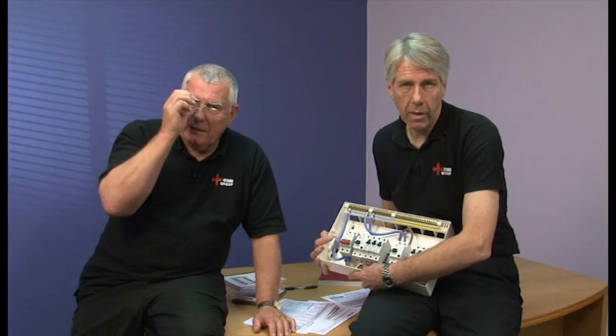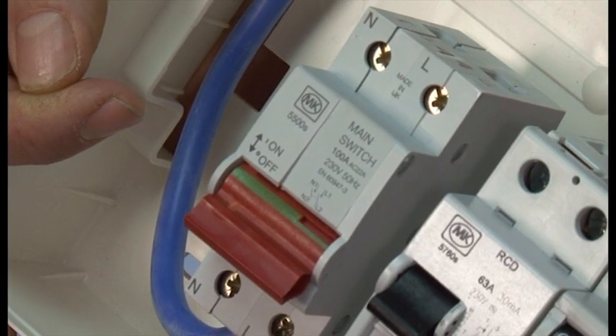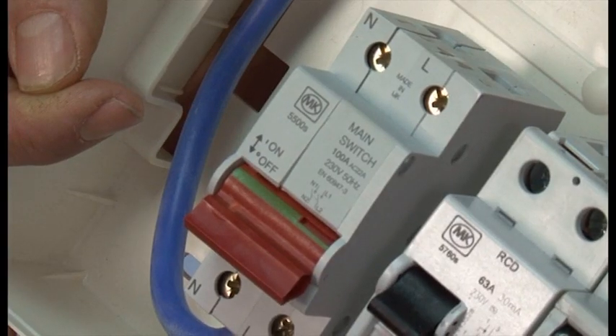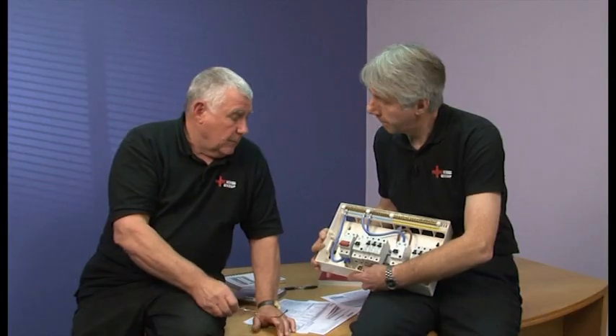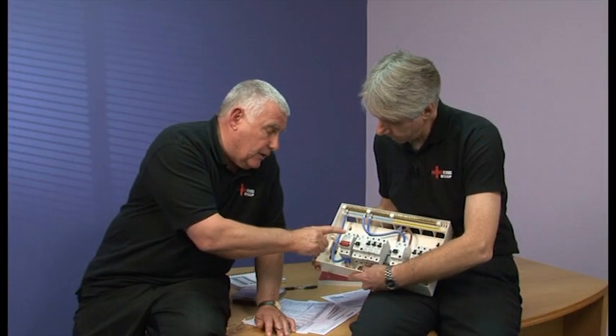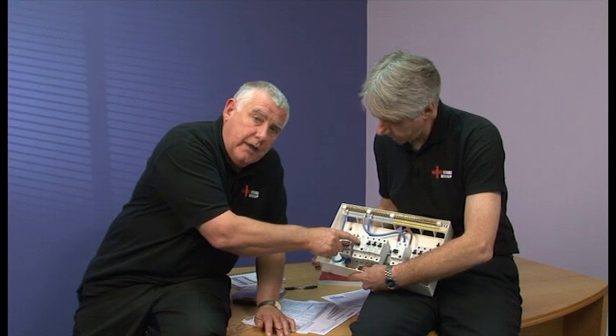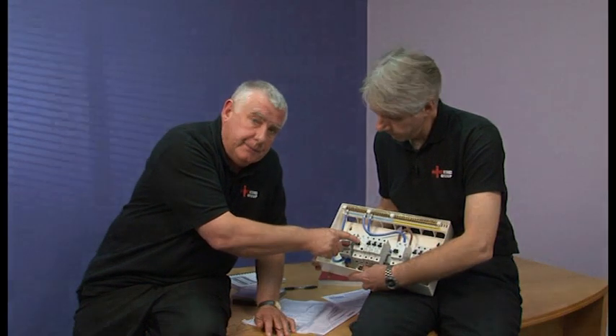The boxes requiring RCD operating current and operating time would only require values where the main switch incorporates an RCD, otherwise not applicable should be written here. Yes, and remember it's the details of the main switch, not the RCD sitting beside it.